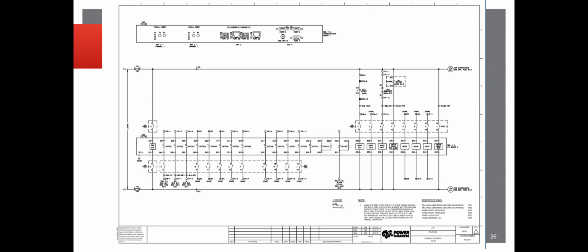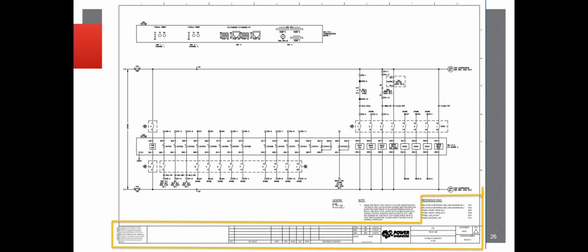We got another example of a DC schematic here. What is circled right there is what they call the revision block. It pretty much gives all the information on this specific drawing, shows who the manufacturer was depending on what kind of drawing, if it's a breaker or something like that. It gives you the rev numbers, so making sure that you have the most up-to-date revision of the drawing is extremely important. When it was, who designed it, any reference drawings that may be associated with it, as well as identifying the equipment, which will be shown right at the bottom right there. So in this case, we have a DC relay schematic that identifies the correct piece of equipment that we're going to be testing.